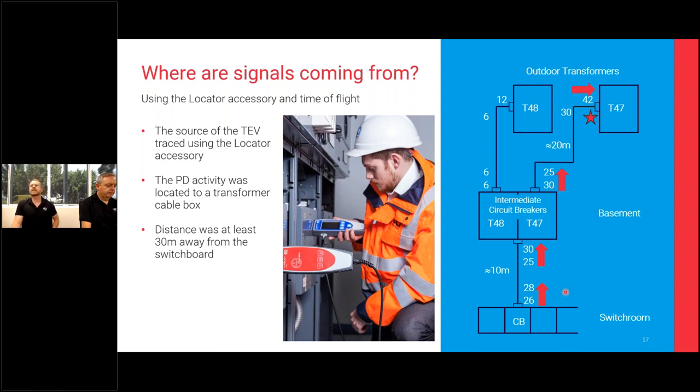So here we have a case study, where this is a switchboard down here on the bottom right-hand side of your screen. We were engaged to come out and survey that switchboard and then monitor it. When we surveyed the switchboard, there were no PD signals detected at all.